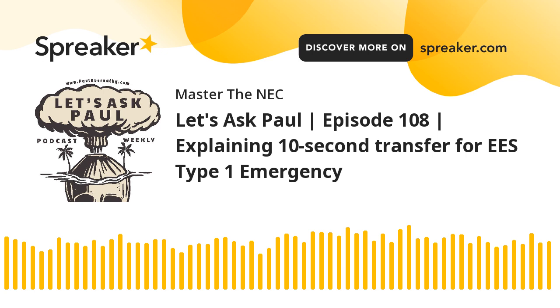Okay. So the first one says, hello, Paul. My question is about 700.12 from the 2017 NEC. I am currently the inspector on a new hospital that was started in the middle of 2017 code cycle. The hospital has a generator building to supply backup power for the essential electrical system. Does just the generator have to be powered up within 10 seconds upon a loss of normal power? Or does the life safety transfer switch also have to engage in these 10 seconds? Thank you.